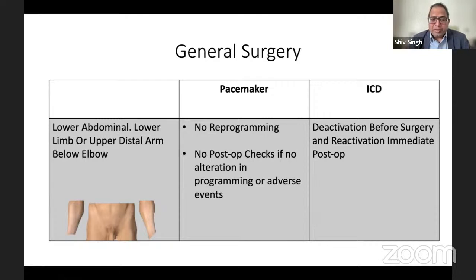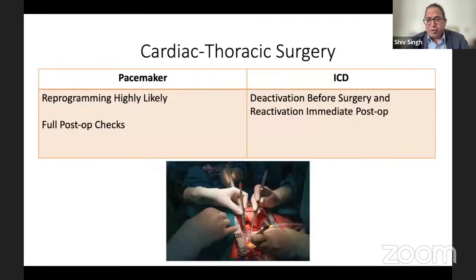If you're operating on the lower abdomen, lower limb, or the upper limb distal, below the elbow, it says no reprogramming is required at all. And there's no need for post-op checks if there has been no alteration in the programming or any adverse events. Cardiothoracic, the current is going to flow through that, so reprogramming is highly likely. So you need a full post-op check. ICDs, like I said, they need to be deactivated.